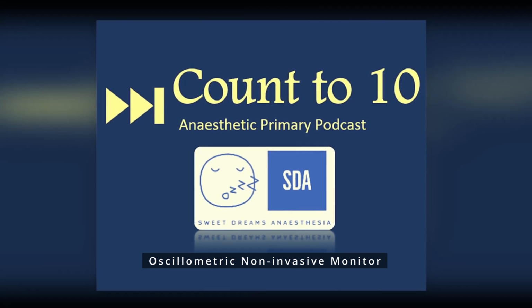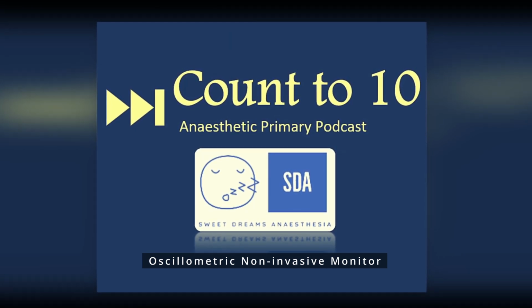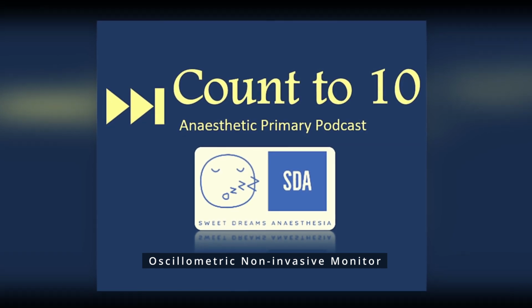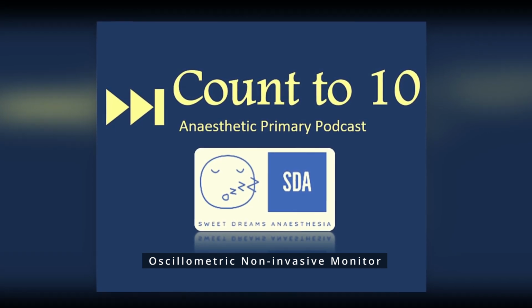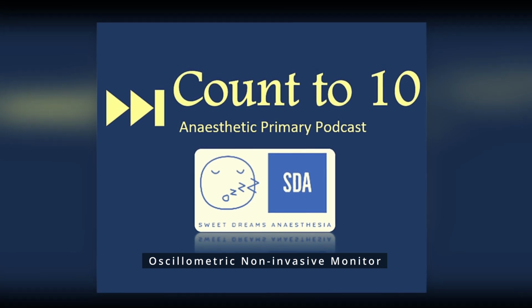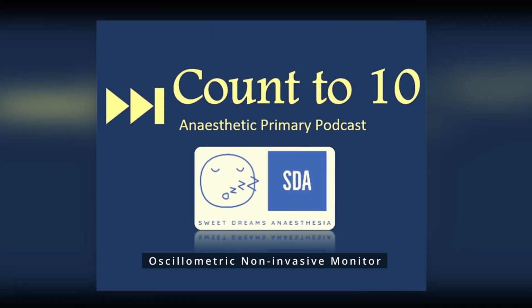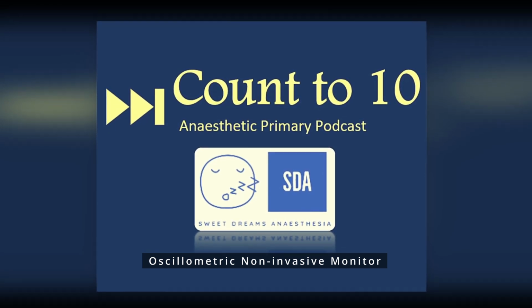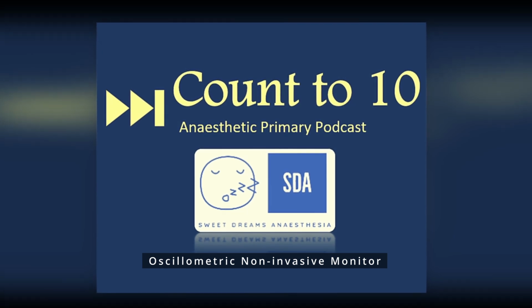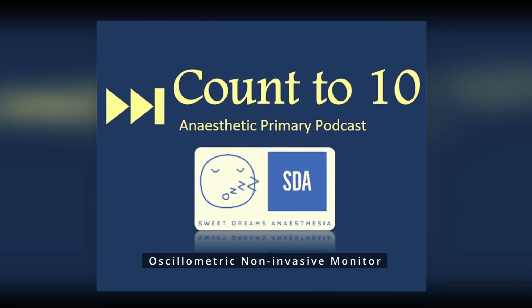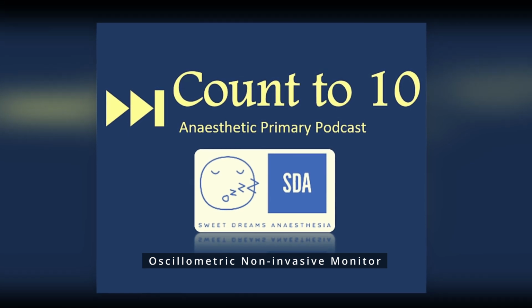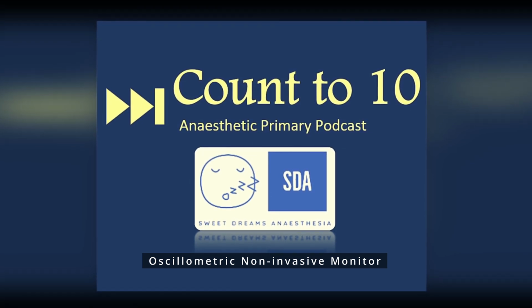You apply the blood pressure cuff on the mid-forearm with the same correct cuff selection as before, and because this is an automated blood pressure reading, when you press start, the cuff is inflated slowly above the patient's blood pressure and then deflated at the same rate of 3 to 5 millimeters per second. While the cuff is being deflated, oscillations are being detected by the transducer. The transducer is recording the amplitude of these oscillations.